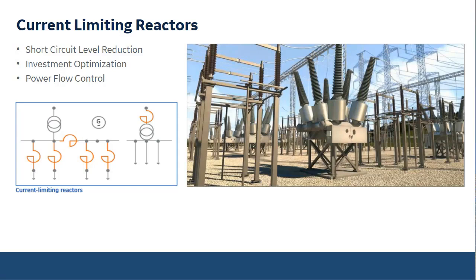And that would not require replacing all the switching devices and all the existing equipment on that existing substation. So by adding impedance, you can save a lot of money compared to reinvesting in all-new switching devices. Of course, when you're adding impedance to the system, we are also adding losses and voltage drop. So there is a capital investment plan study that needs to be done to see if the losses from the reactors would make more sense than spending all that money on new switching devices.